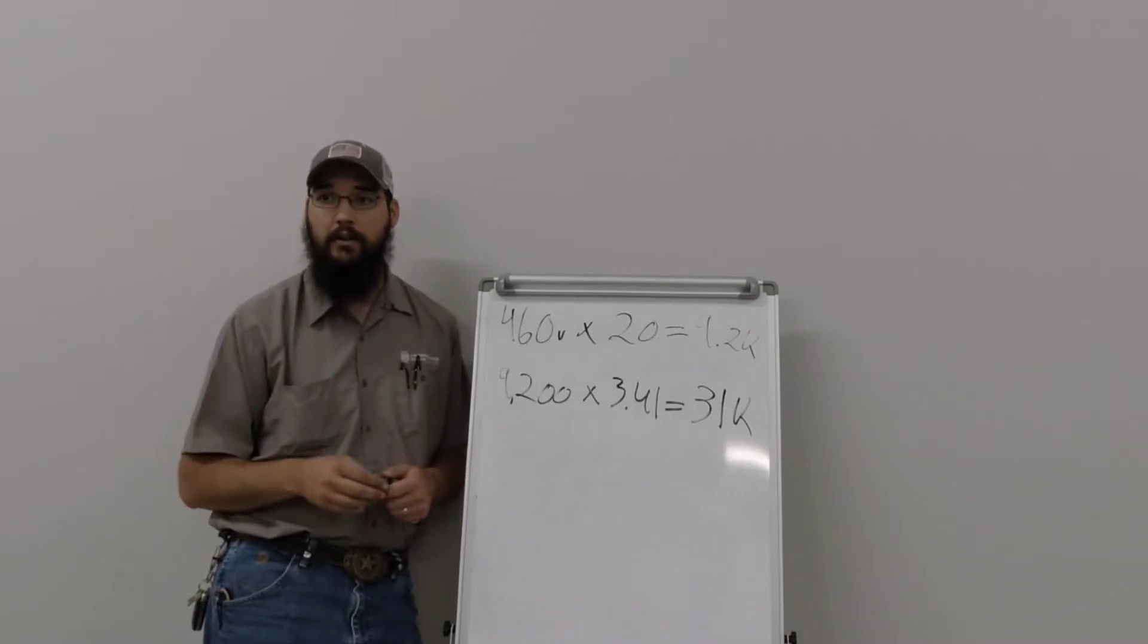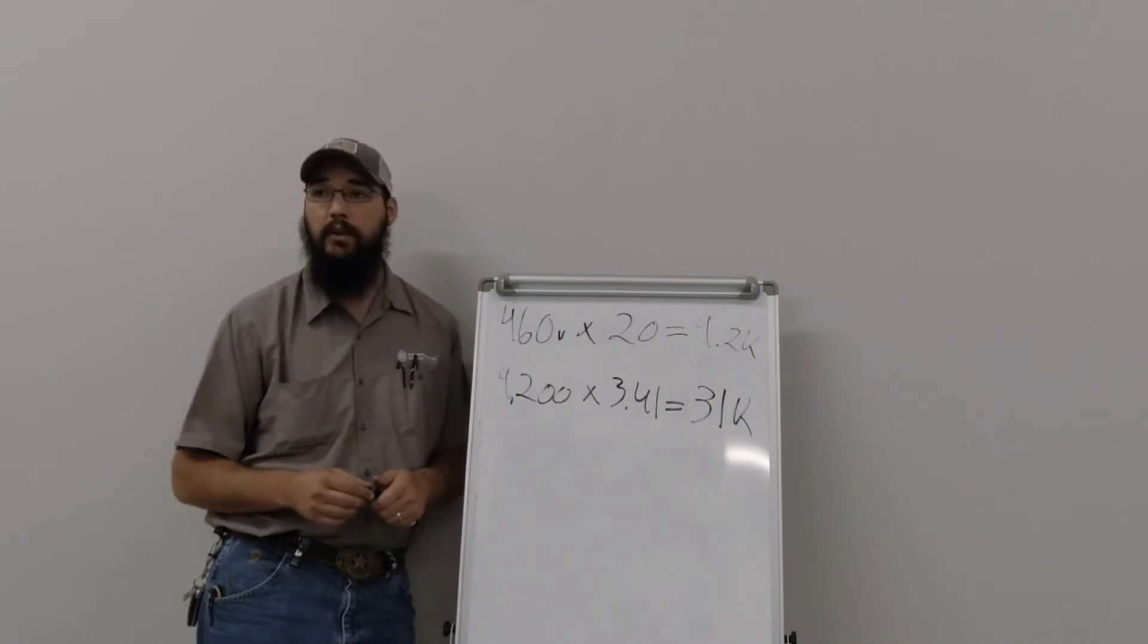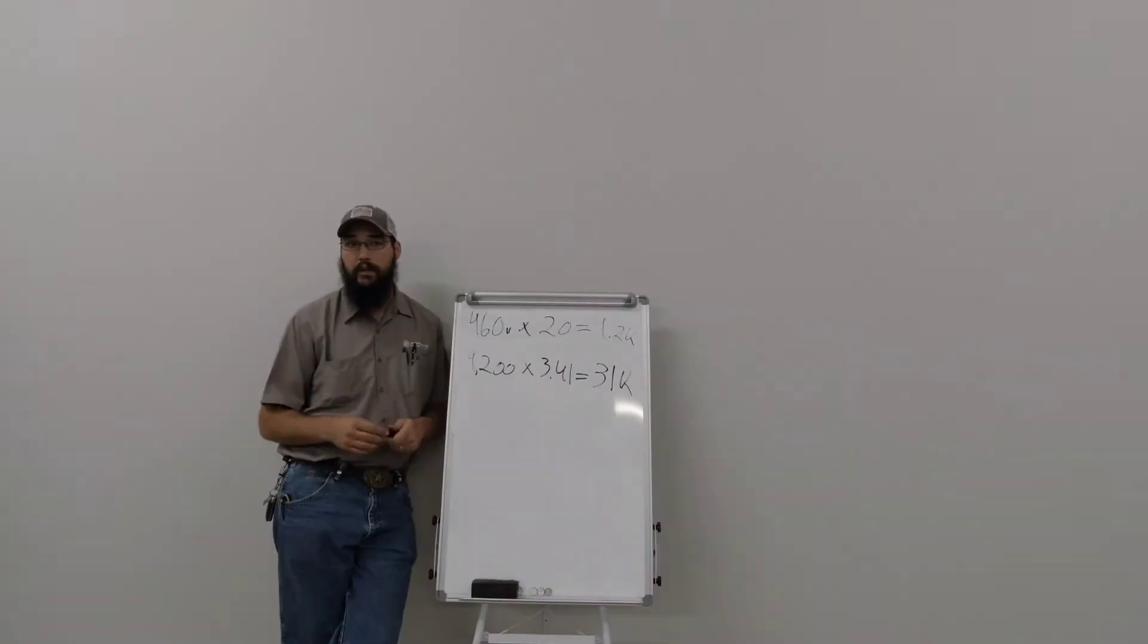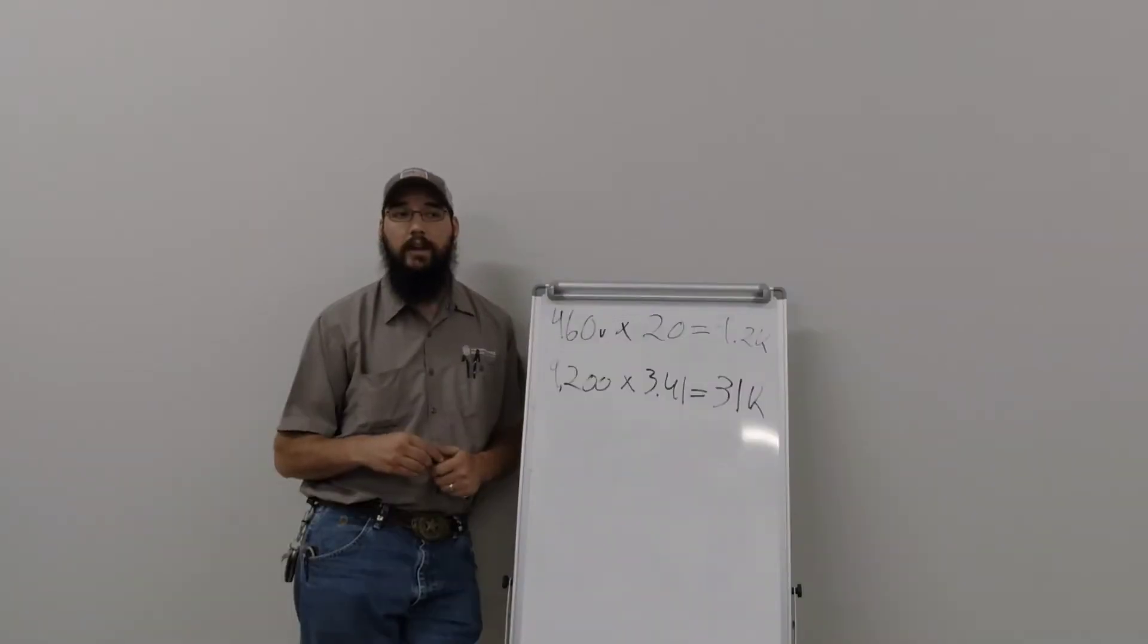I'm kind of getting off on a tangent here, but you can help diagnose a compressor based off discharge superheat. So if you've got a discharge superheat, it's running 60, 80 degrees, even though your suction superheat was 12, chances are that that compressor is starting to have problems.